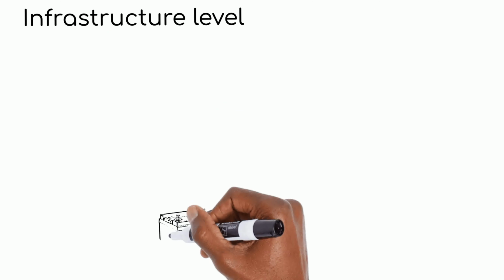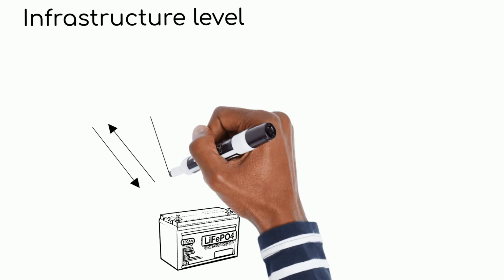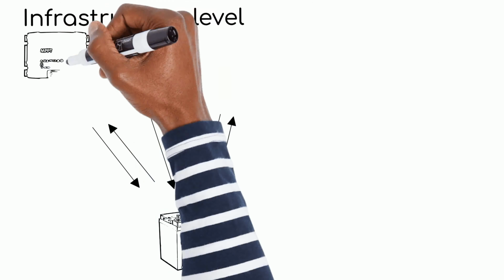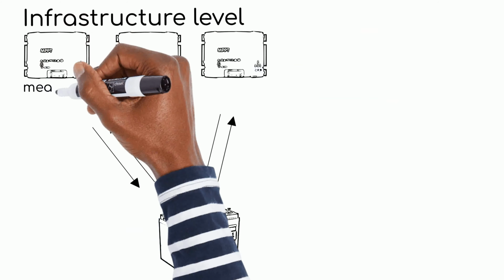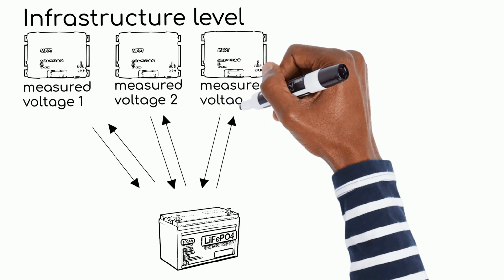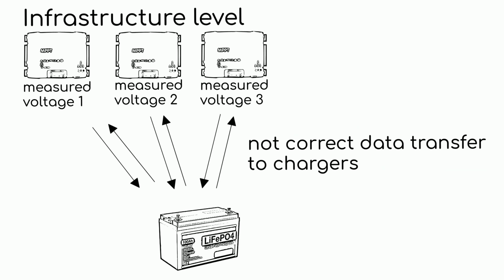There are usually several charging sources on a boat. Each of these is connected to the battery through its own conductor. The conductor may differ in length and cross-section. As a result of this, we can observe a voltage drop from the charger to the battery. Most chargers measure battery voltage through their power leads. The voltage at the charger terminals may differ significantly from the actual battery voltage. For example, the charger detects that the battery voltage is 3.45 volts per cell and goes into absorption mode, but in fact, the battery has not reached it.